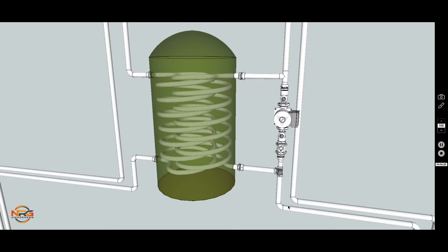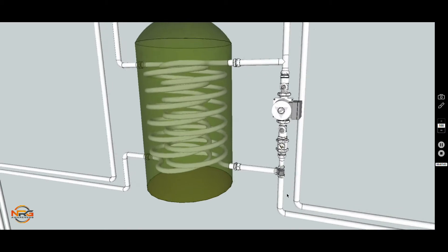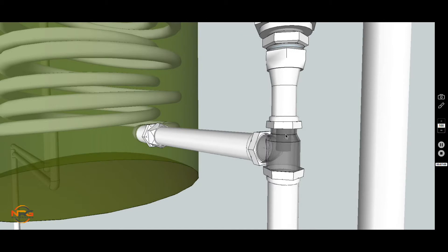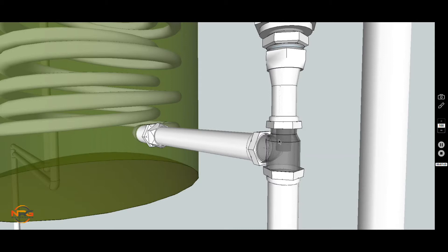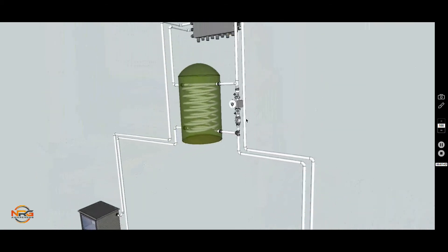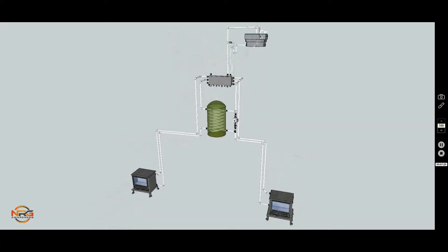But if the return pipe ever goes above, say, 55 degrees, then a stat would turn on this pump. In that situation, water would be pulled down by the pump and be pushed open the non-return valve and pushed down through the injector T. The injector T has a smaller tube or pipe inside the T, which can be made by the plumber or purchased. The idea being that the pump will be forcing water through a narrower chamber or narrower pipe, and when it does, it increases velocity. When it injects out at this point, it will create a vacuum by the Bernoulli principle or the Venturi principle. That will cause a suction effect on this pipe, which will make the cylinder heat even better. At the same time, the pump will force this water down along the pipe and cause much more water to travel through the primary circuit and out into the solid fuel heat exchanger. Therefore, this will work by far faster because this pump is operating than this one.